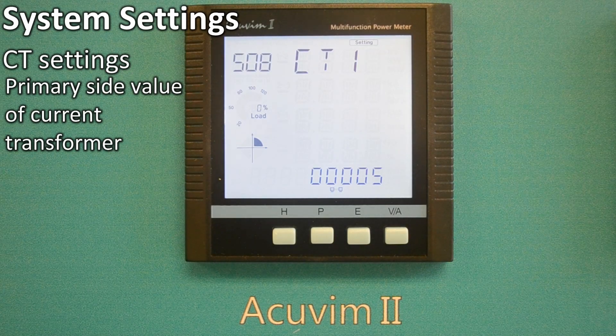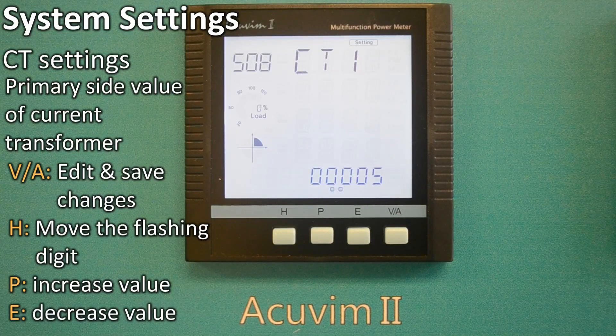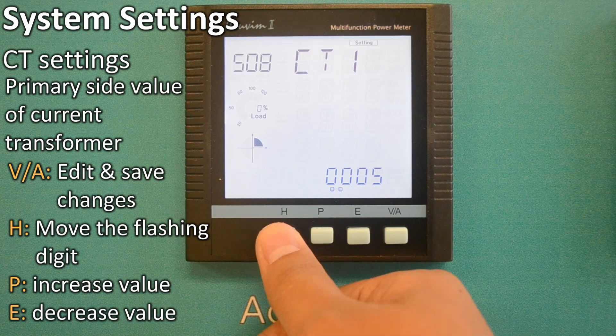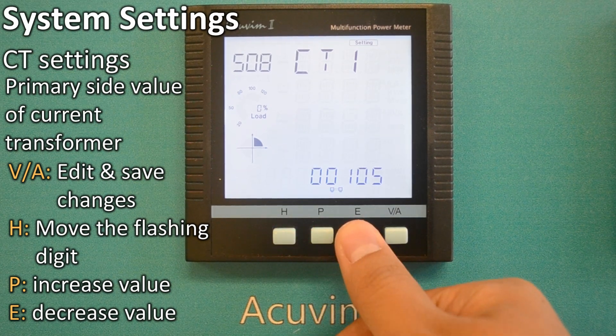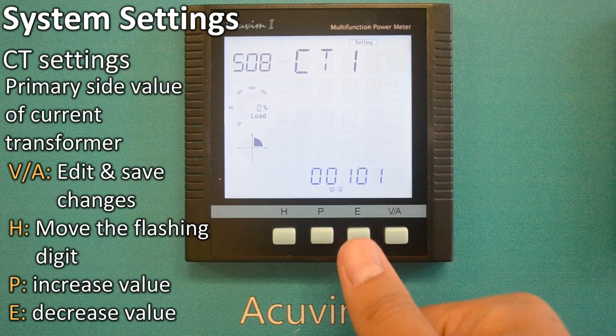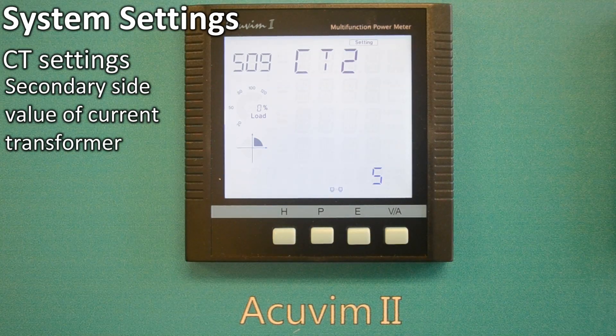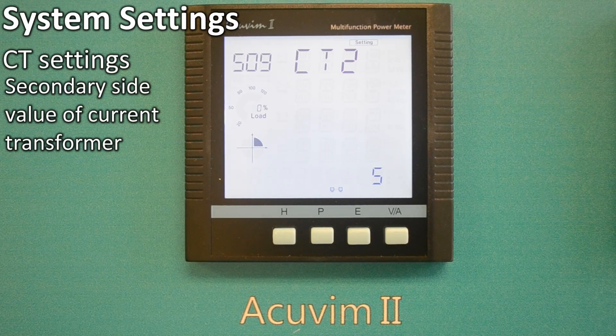CT1 5 amps means the primary side value of the current transformer. If a 100 amp to 5 amp CT is used, this screen should be 100. To make a change, press VA and the setting will flash, indicating it is ready for editing. Press H to move the flashing digit, press P to increase or press E to decrease the value, making the change, for example, to 100. Pressing VA will save the change. CT2 5 amp or 1 amp, depending on the meter option you choose, means the secondary side value of the current transformer. It should be left at factory setting of 5 amps or 1 amp.